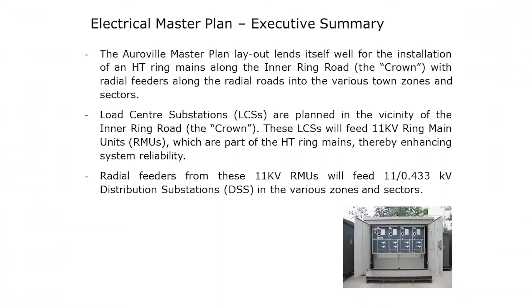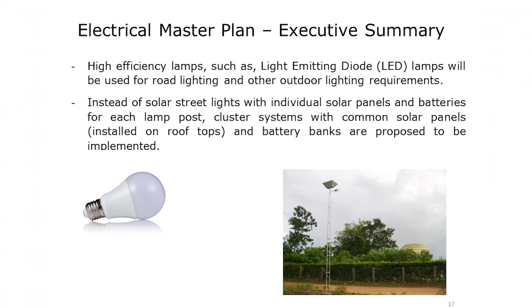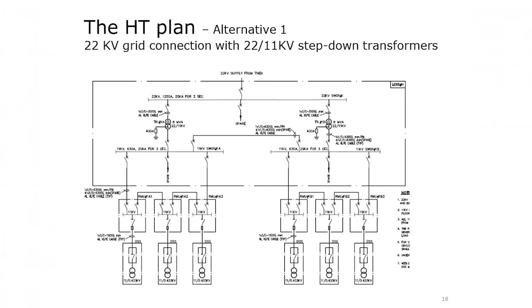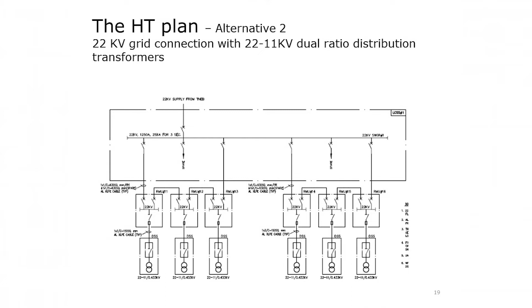I won't bother you with all the details, let me go straight to the conclusion. Plan 1: we keep the 22 kV from TNB until they change, and step it down ourselves. Option 2 was dual ratio transformers, so they can be switched over from 22 to 11 once the 11 comes. We initially went with this option, and the first 4 or 5 transformers are like this.